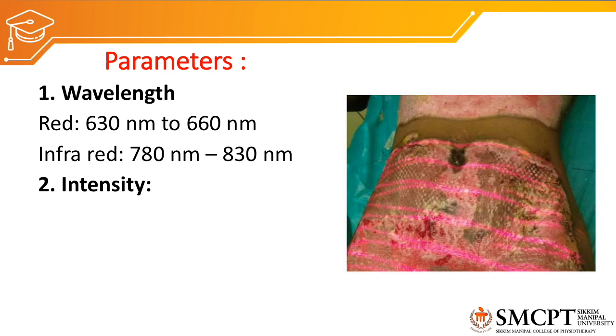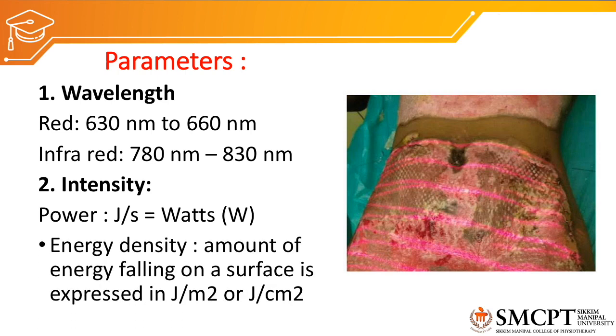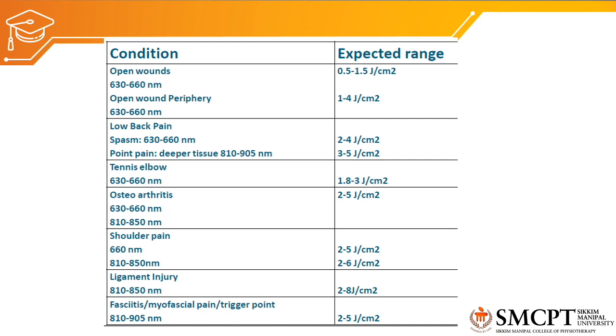The second parameter is intensity. Power is joules per second, also called watts, and energy density is the amount of energy falling on a surface, expressed in joules per meter square or joules per centimeter square. The intensity of laser used for treating wounds, low back pain, tendinitis, bursitis, etc., should be given in joules per centimeter square or joules per meter square.